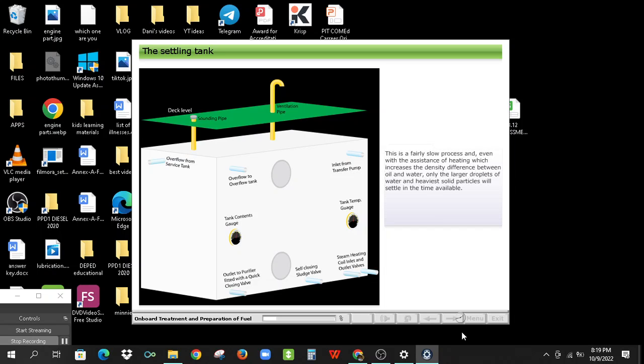This is a fairly slow process, and even with the assistance of heating, which increases the density difference between oil and water, only the larger droplets of water and heaviest solid particles will settle in the time available. As we will see later, we need to use other means to remove the remaining water and dirt from the fuel before we can use it.